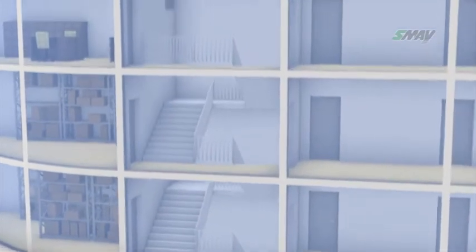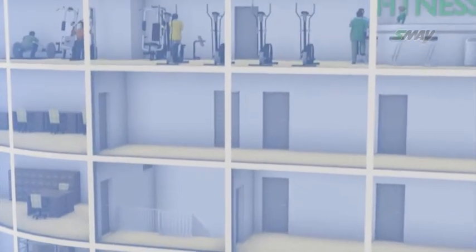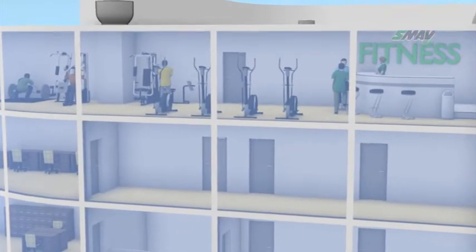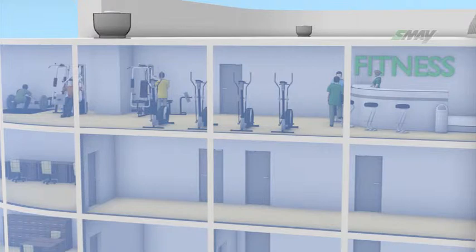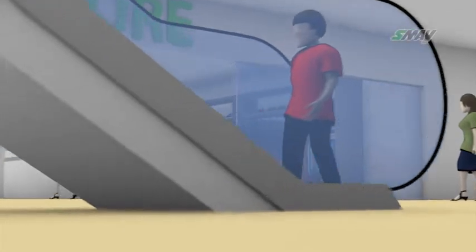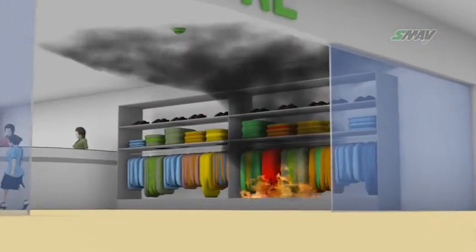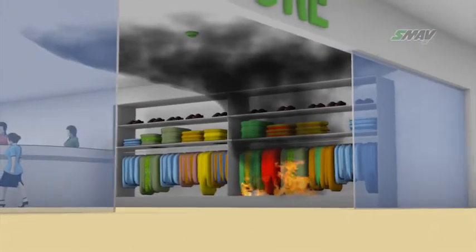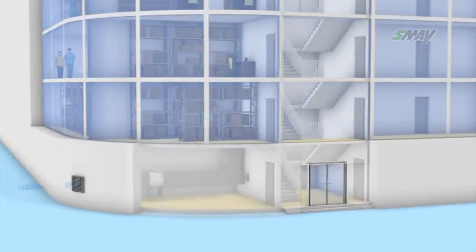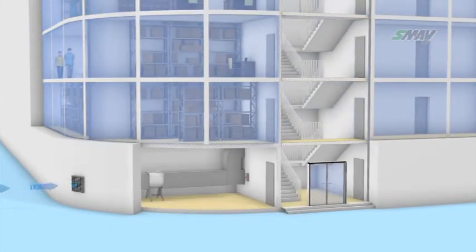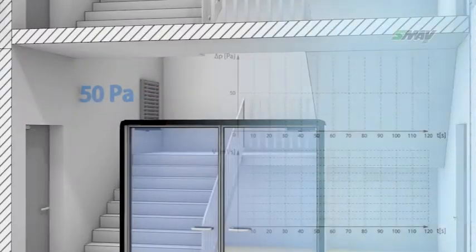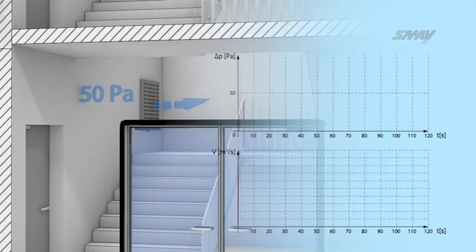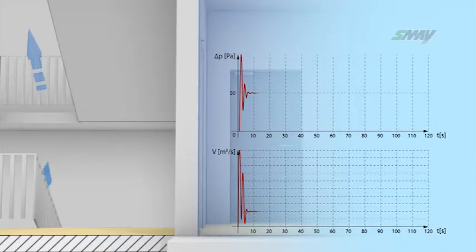There can be other rooms above them, which is why it is impossible to install barometric overpressure dampers. At the same time, the system has to cope with the problem of great variations in airflow supplied to the staircase. During the realization of pressure criterion, the airflow is small, and during the evacuation, the required flow is even 10 times bigger, which poses a problem in the precise control of the system.